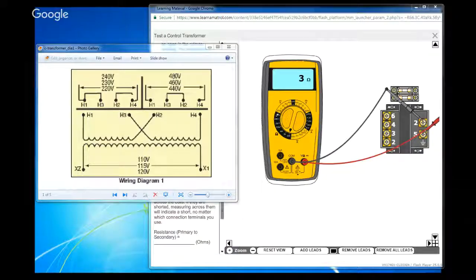Okay, well, let's talk a little bit about control transformers. You'll be doing some skills using a simple transformer. We've already seen that you'll be using what's commonly called a primary and secondary winding. But when you get out into the real world, most control transformers you will encounter, for dropping our high three-phase voltage to a lower voltage that we can use in our panels, will be multi-tap. That's because manufacturers do not want to create separate transformers for different voltages.